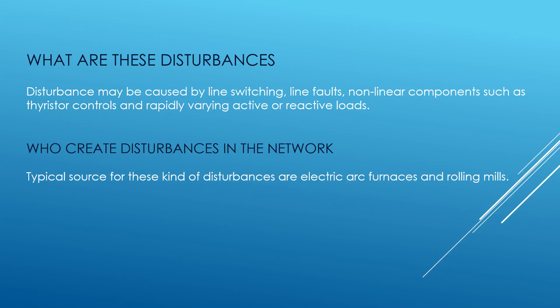Now let's look at these disturbances and who creates them. A disturbance is a power system imbalance caused by changes in reactive power requirement due to various reasons — this could be line switching, line fault, network short circuits, line and generator disconnection. Typical sources for these kinds of disturbances are electric arc furnaces and rolling mills. These disturbances result in harmonics that load the supply network and cause voltage fluctuations.